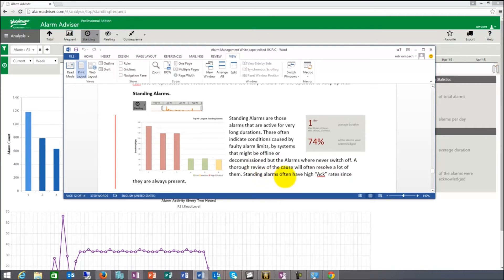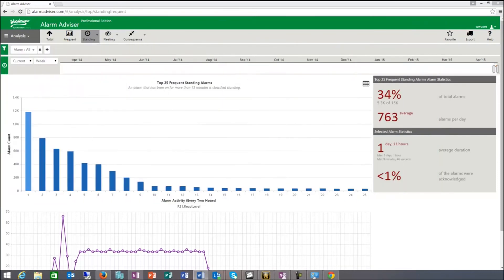Standing alarms often have a high Ack rate since they are always present. With frequent, they come very often. But standing, they don't come often, they're just always there. These are whatever control room you go, you always see this long list of unacknowledged alarms. Typically, those are the standing alarms that basically are always on, no matter what the condition of the plant is at that point.